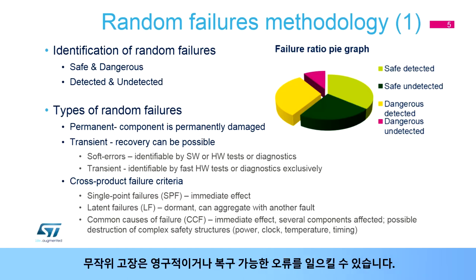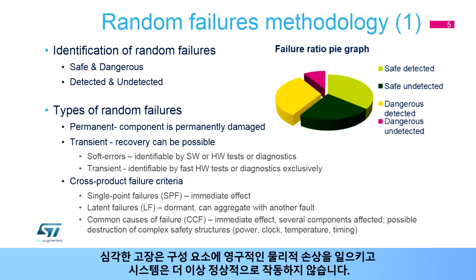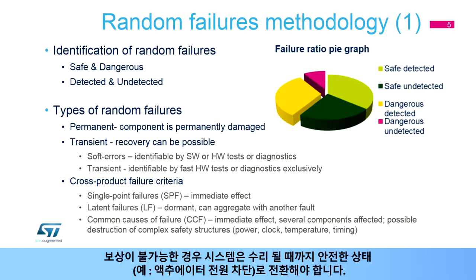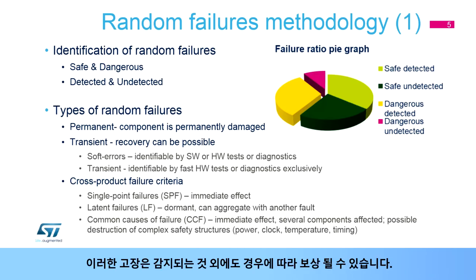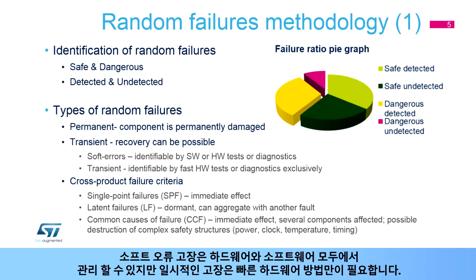Random failures can cause permanent or recoverable errors. Hard failures cause permanent physical damage to the component, and the system is no longer able to operate normally. If no compensation is possible, the system has to be put into a safe state, for example by cutting power to actuators, until it is repaired. Random transient or soft errors can be correctable, and some kind of recovery process can be applicable. In addition to being detected, these failures can also be compensated in certain cases. Soft error failures can be managed by both hardware and software, while transient failures need fast hardware methods exclusively.